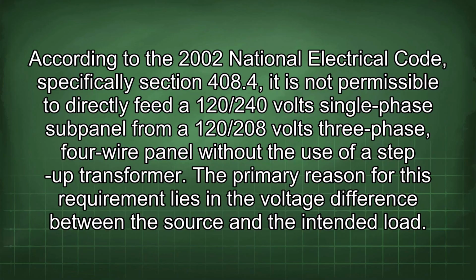According to the 2002 National Electrical Code, specifically Section 408.4, it is not permissible to directly feed a 120/240 volt single-phase subpanel from a 120/208 volts three-phase 4-wire panel without the use of a step-up transformer. The primary reason for this requirement lies in a voltage difference between the source and the intended load.